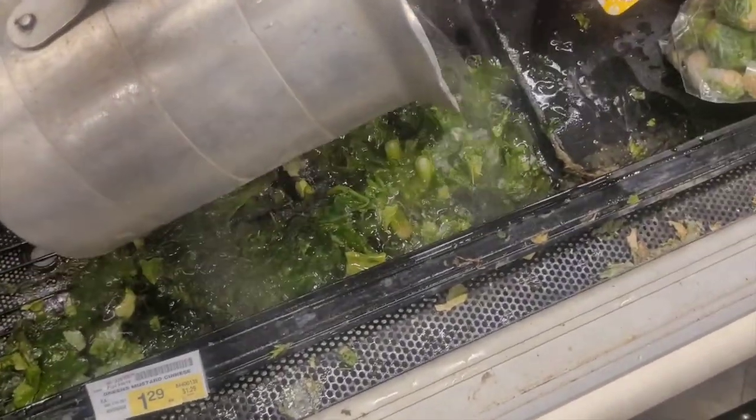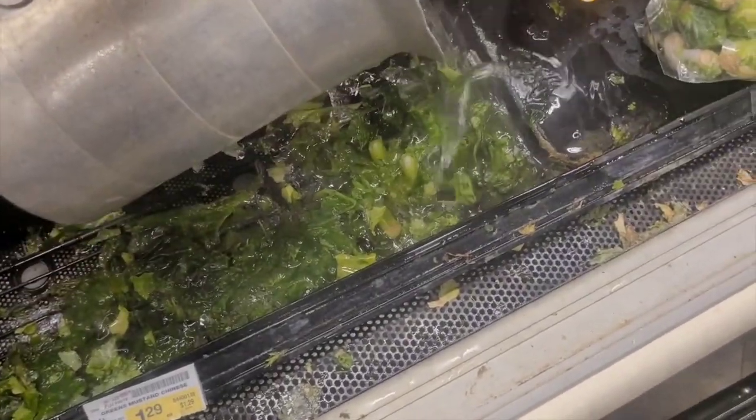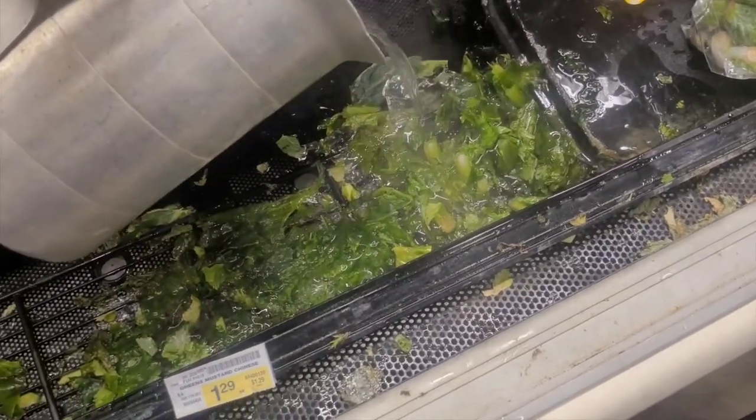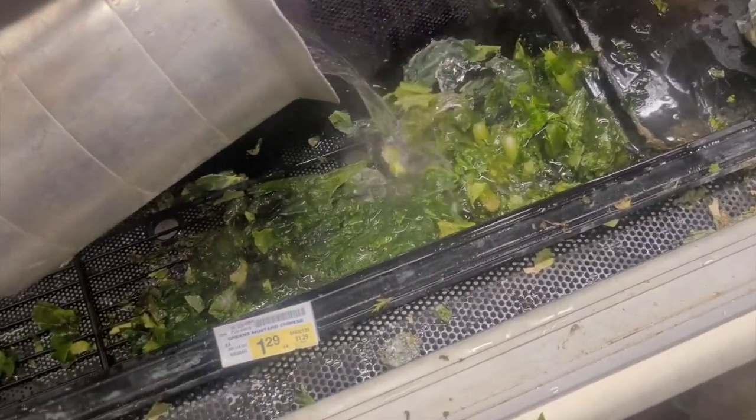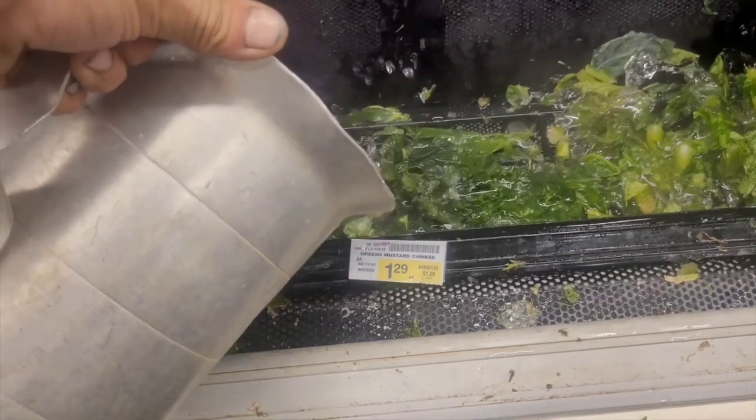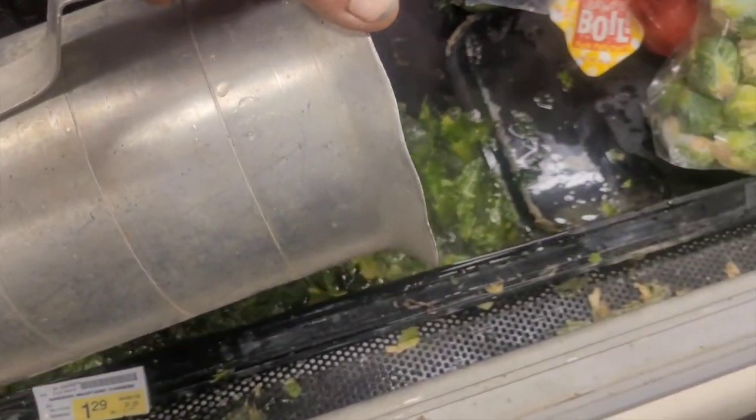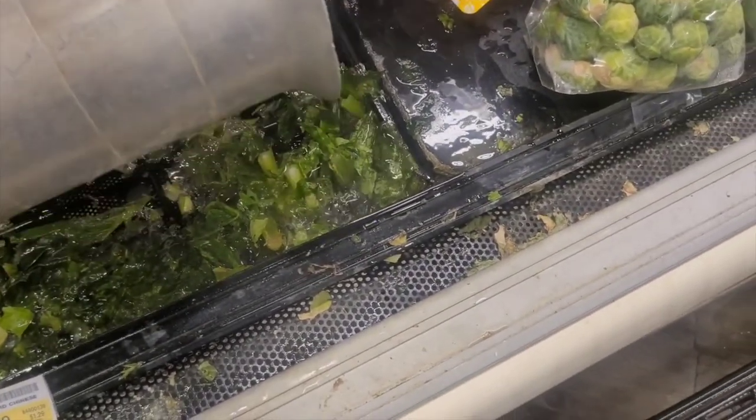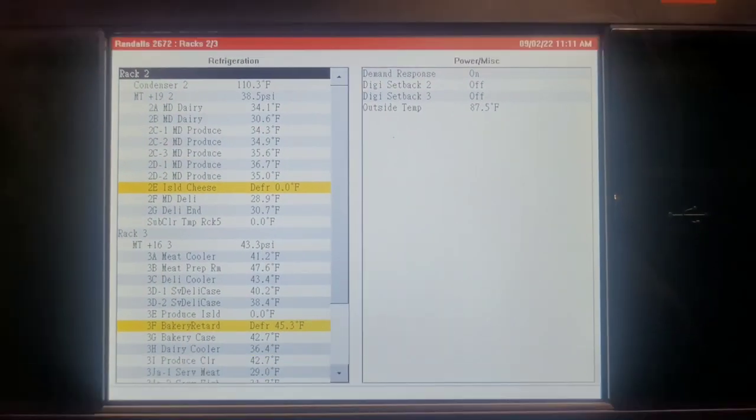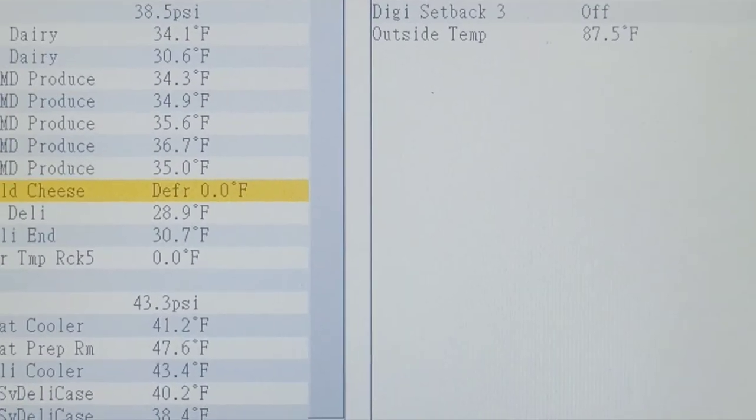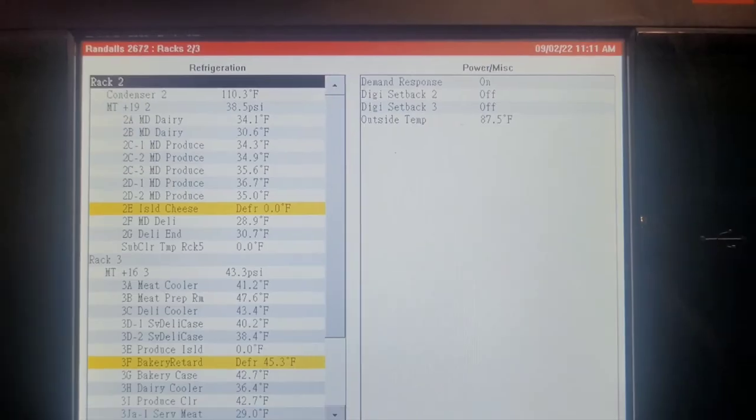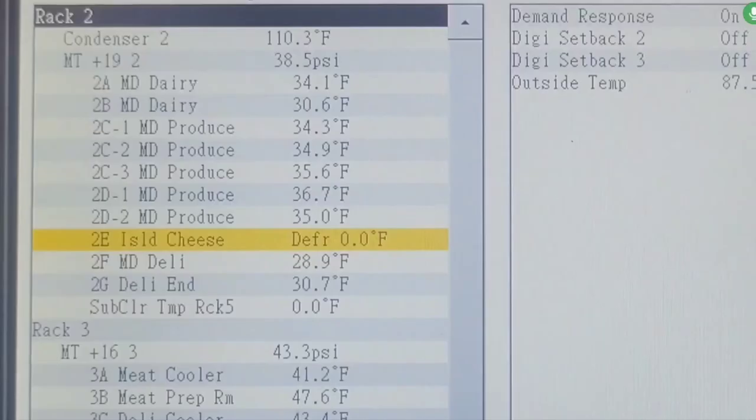To finish up, I took some hot water, went down there, added heat to the case with this hot water. That's not my job, but it helps me, because by adding heat, I can make sure that the unit's going to get hot. If I set it too high, I can always adjust it back down or whatever. But by adding heat to the case, that's how I'm testing what I did. Back up there again at 11:11, I added heat to the case, and so we're sitting at 36.7 and 35. That's exactly what I wanted right there.